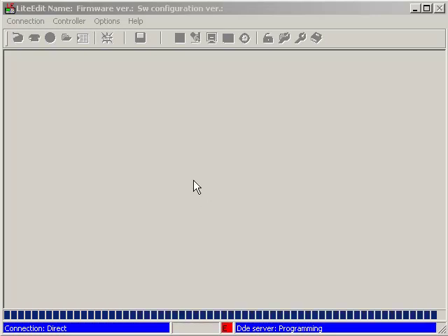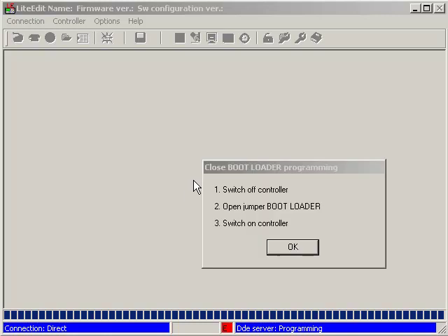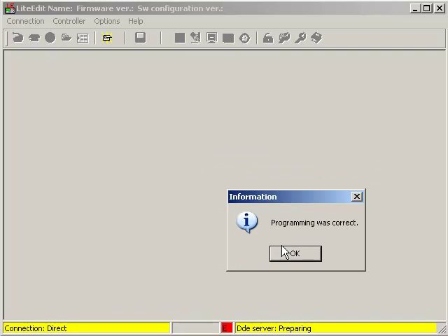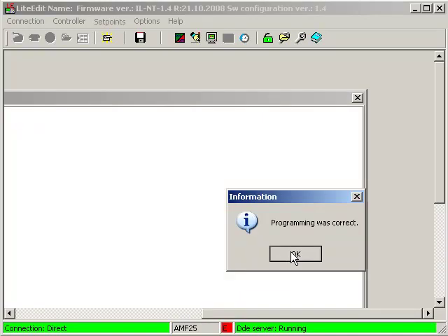LiteEdit is about to finish programming of the control now and the instructions window is displayed again, as you can see. Switch control off first, open the boot loader jumper, and switch the control on again. Click OK when it is done. Control programming was correct, as you can see.